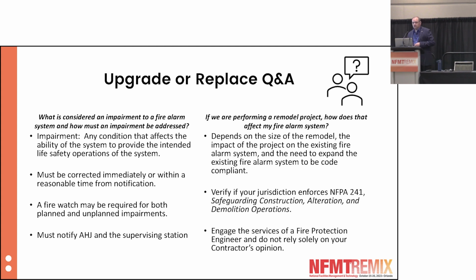They may have to institute a fire watch at the facility manager or owner's expense for both planned and unplanned impairments. A planned impairment might be a tenant finish, where you're impairing a portion of that fire alarm system for some period of time, but it may still need a fire watch done in that area. An unplanned fire watch is very expensive, and that's where you might have roving guards who have to walk the building once an hour. You might have to get a permit from the local AHJ to make that happen, to provide the reporting. It gets very, very expensive.